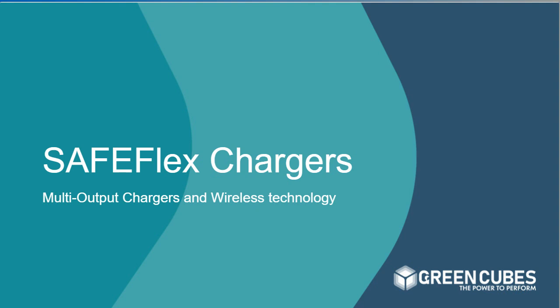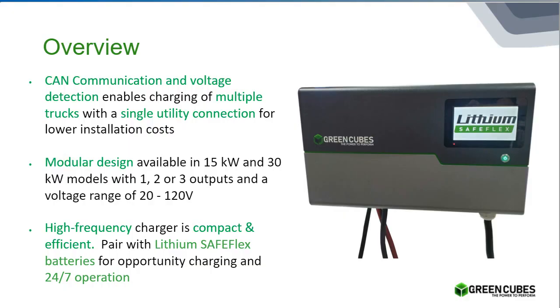Okay, so if you need to upgrade your charger in order to do opportunity charging, we do offer a multi-output charger that has a lot of really good features for opportunity charging. The SafeFlex charger utilizes CAN communication to automatically start and stop charging based on the demand given by the SafeFlex lithium-ion batteries that we offer. This allows for smart and safe charging of the material handling equipment without the manual input of the operator to start and stop the charging.